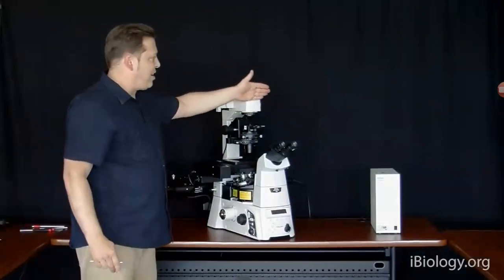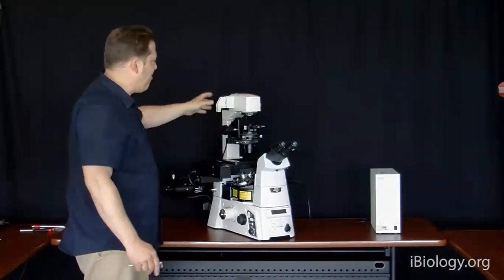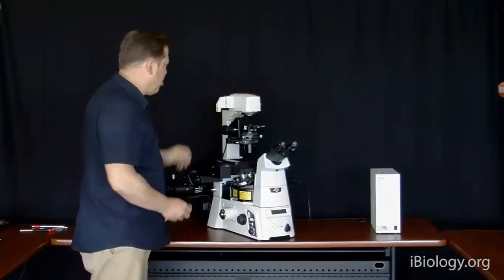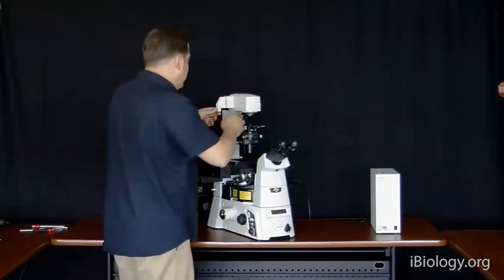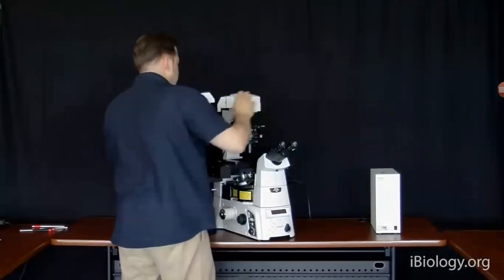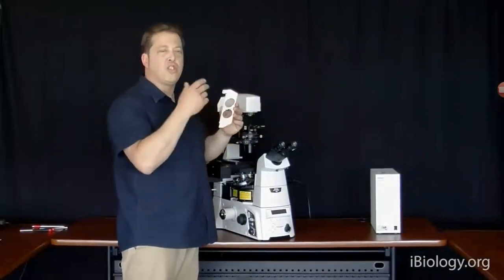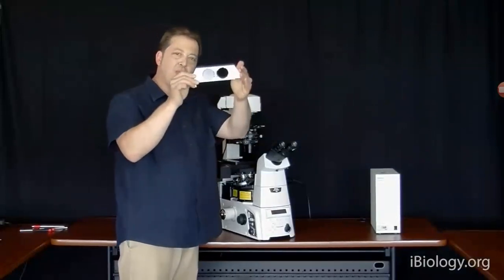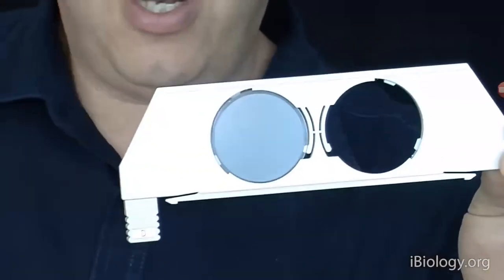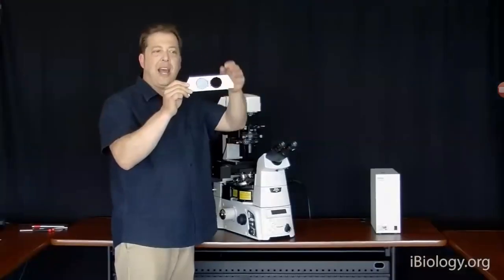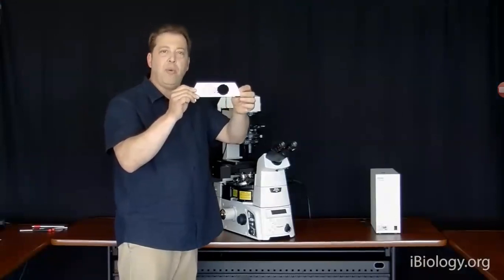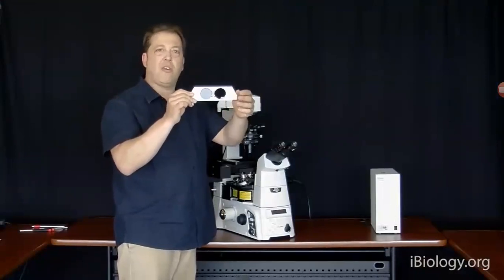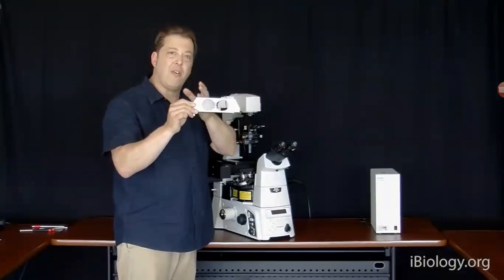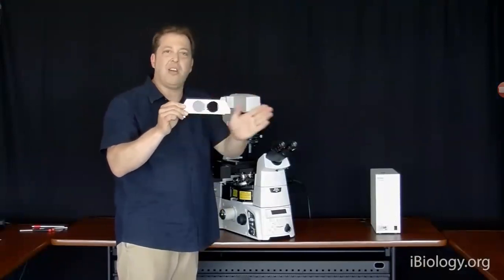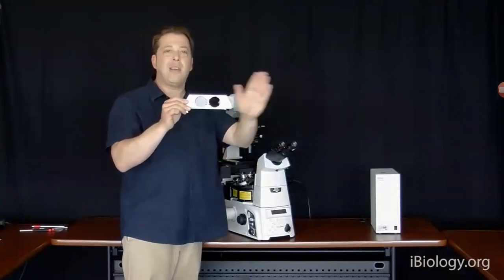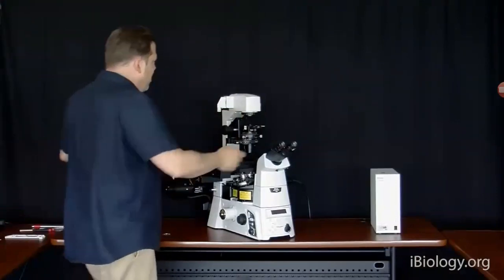So next, transmitted light comes through here. This is all aperture space. There's nothing in focus in there, and that's why we put our filters in this location. We've got several filters and a diffuser in this microscope. Anytime you have a halogen bulb or a bulb with a filament, we normally want to soften the edges of that sharp filament. We use what's called a diffuser. This diffuser is just a frosted piece of glass or plastic, and it breaks down those harsh edges of the filament in the bulb and softens it. We also use a technique called a fly eye lens that, instead of having a single filament, will make thousands of images of that filament, basically diffusing it throughout the field of view and giving you very even illumination.